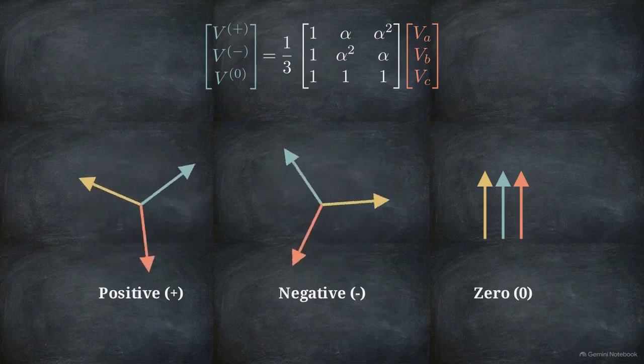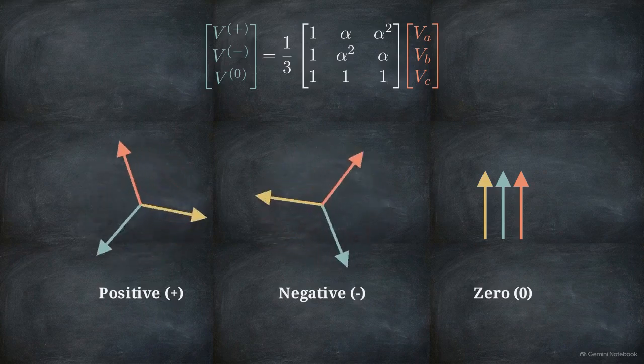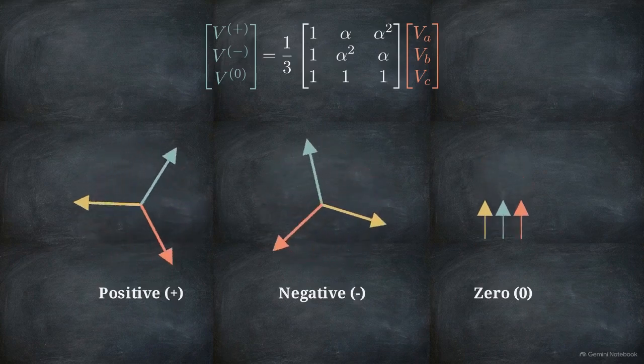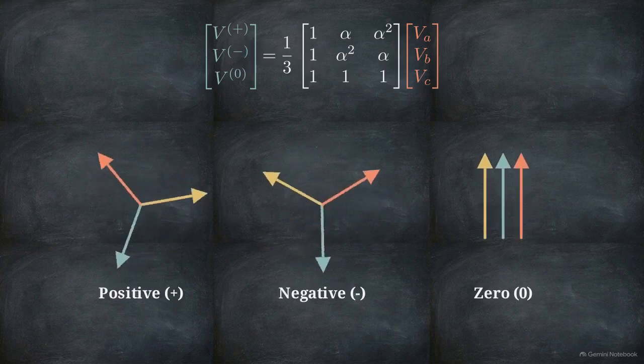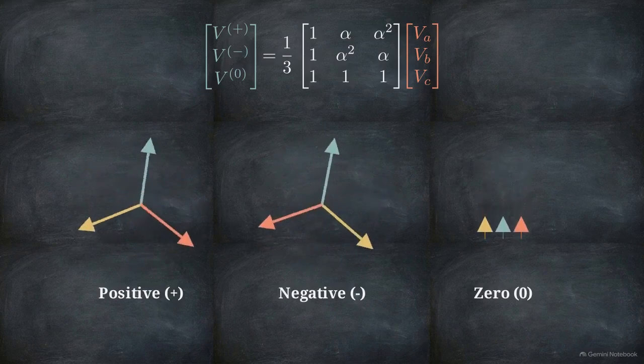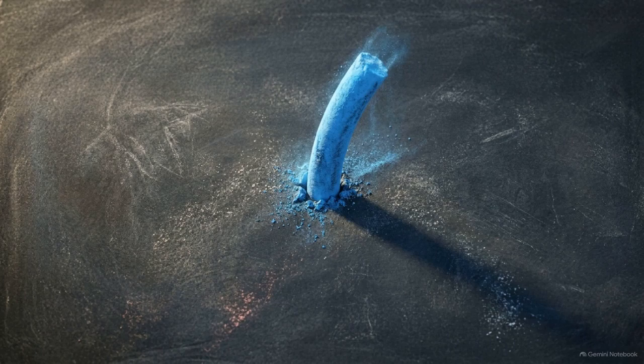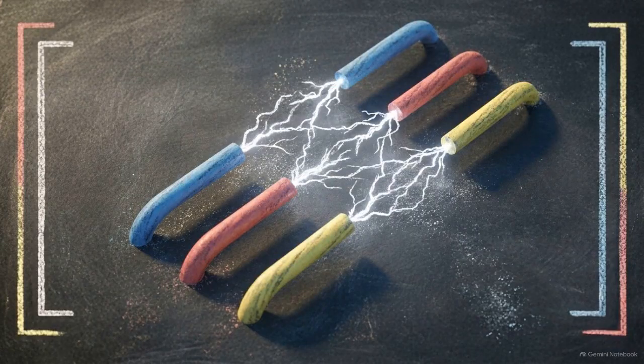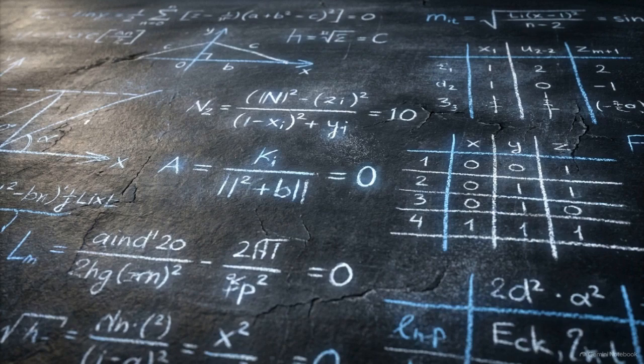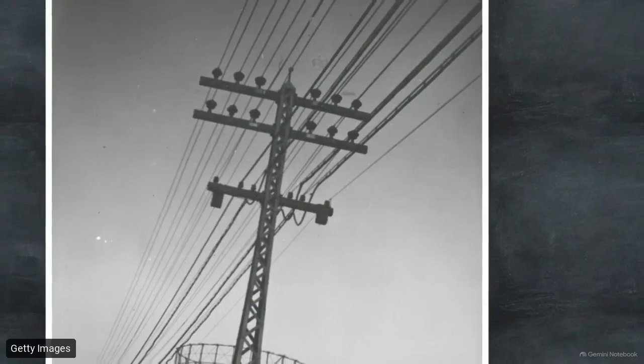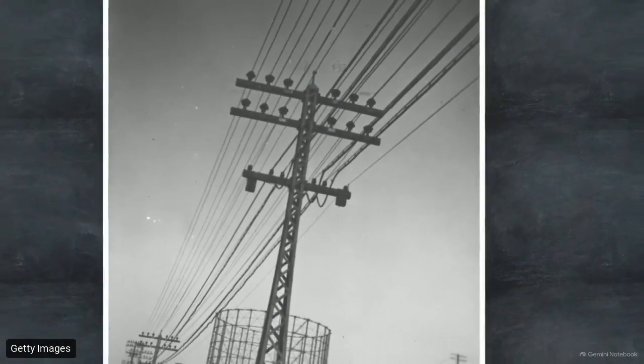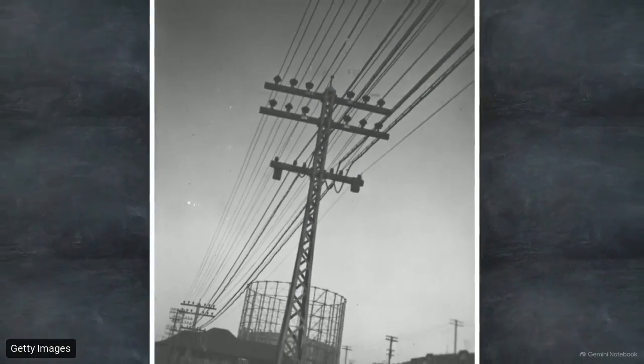It extracts three sets of balanced vectors: positive sequence, rotating standard ABC, negative sequence, rotating reverse, and zero sequence, pulsing perfectly in phase. Because it is a systemic property, a sequence component cannot mathematically exist in one isolated phase. It requires the interaction of all three phases simultaneously. Translating these voltages into sequence coordinates is highly organized, but it is merely the setup. The true power of the Fortescue method lies in how it applies to the grid's physical infrastructure.